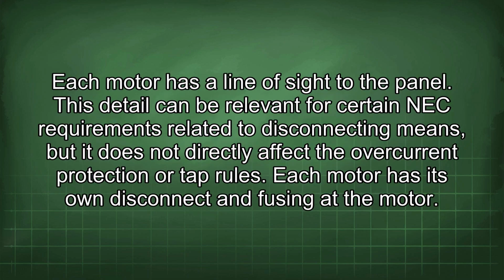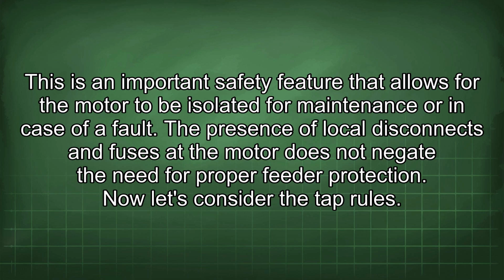Each motor has a line of sight to the panel. This detail can be relevant for certain NEC requirements related to disconnecting means, but it does not directly affect the overcurrent protection or tap rules. Each motor has its own disconnect and fusing at the motor. This is an important safety feature that allows for the motor to be isolated for maintenance or in case of a fault. The presence of local disconnects and fuses at the motor does not negate the need for proper feeder protection. Now let's consider the tap rules.